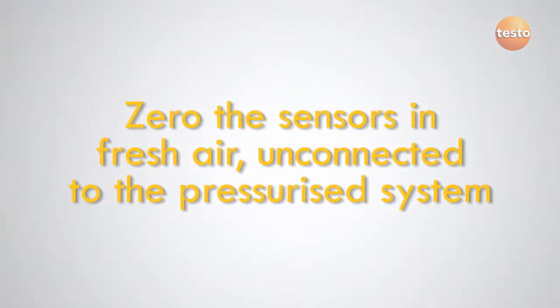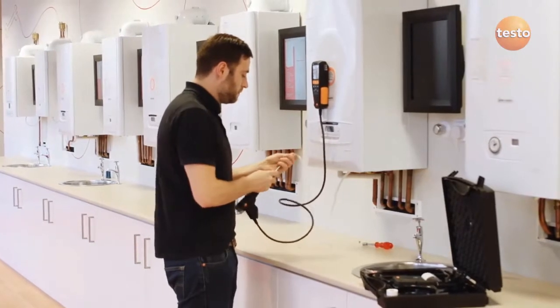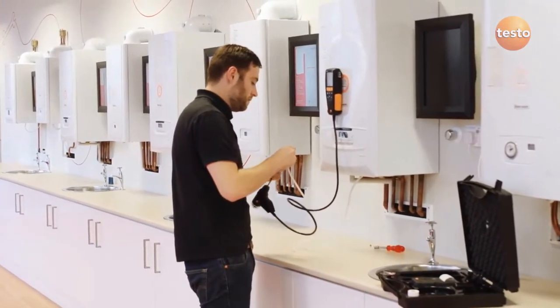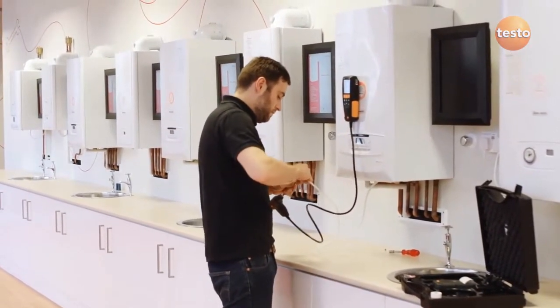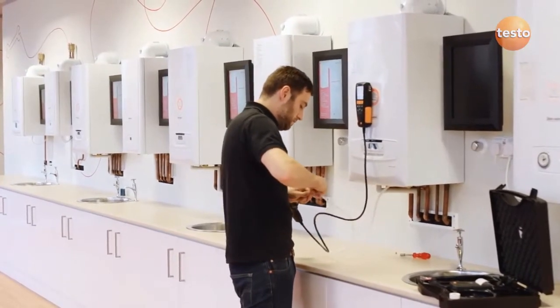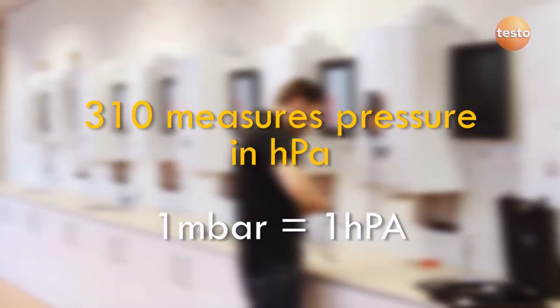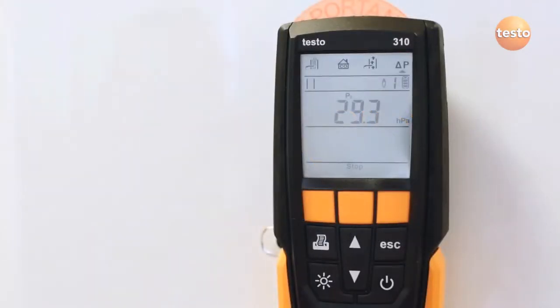Again, it's important that the sensors are zeroed in fresh air, not connected to the pressurized system. When the pressure sensor has been zeroed, you can fit the silicone hose to the probe and connect it to the test point to measure the gas pressure. The 310 displays pressure in hectopascals, but if you prefer to record it in millibars, then just remember that 1 millibar is equal to 1 hectopascal.